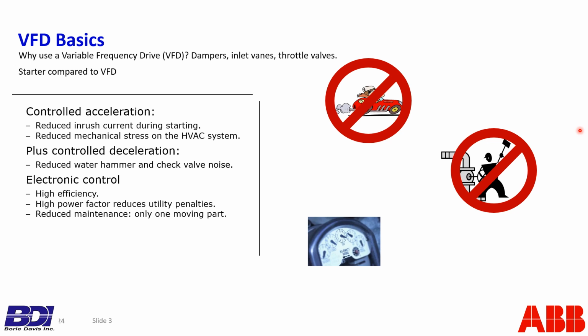Now, the other niceties of a drive is a higher efficiency, because I'm not turning on and turning off. I've got a system that varies the speed to maintain the comfort or flow or whatever you're trying to maintain in the system, as opposed to turn it on for a while and turn it off for a while, or waste energy across a throttle valve or dampers or inlet vanes. So we directly control the speed of the motor, which gives us fewer losses. And since there's no throttle valves, inlet vanes, or dampers anymore, those things that drop pressure and wear out, well, that's no longer the case. Okay, so reduced maintenance.